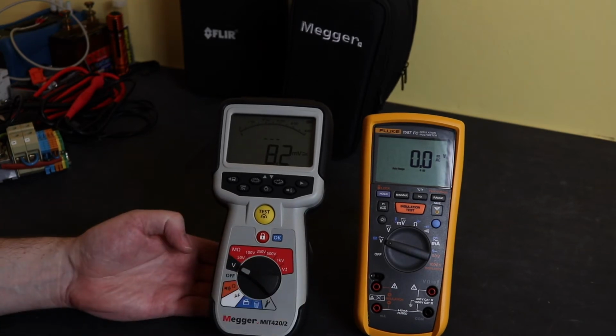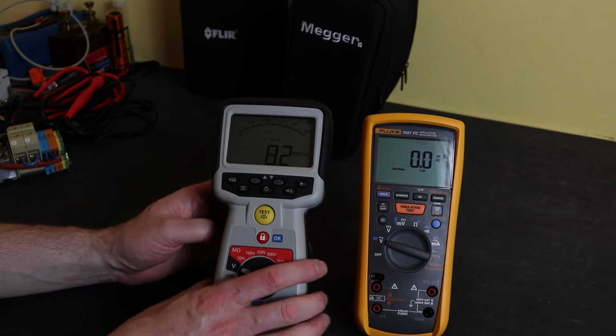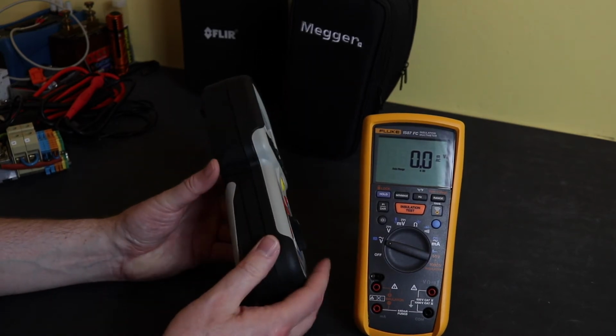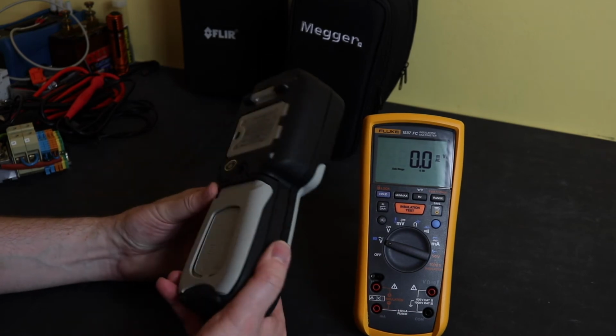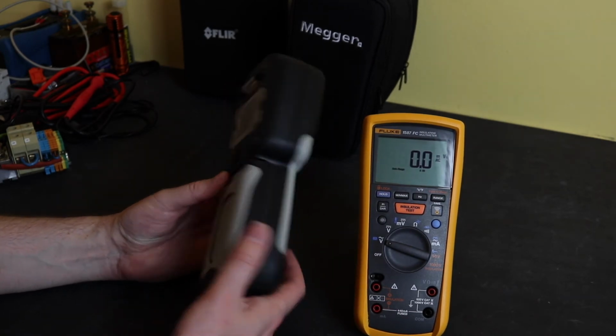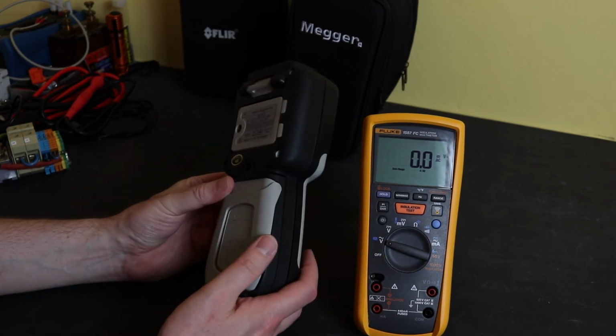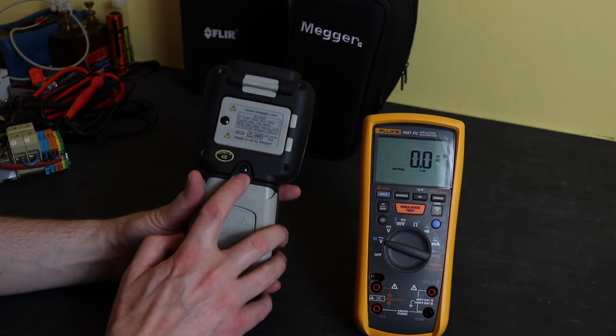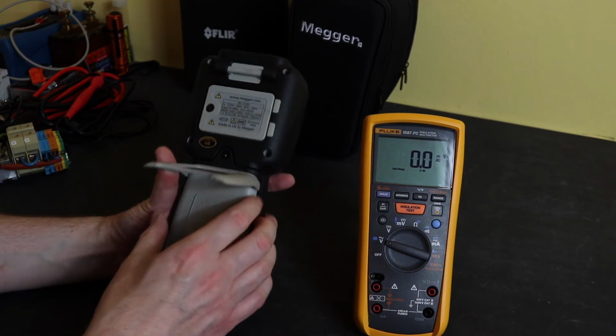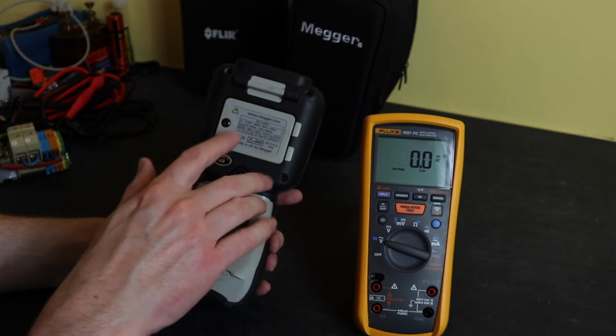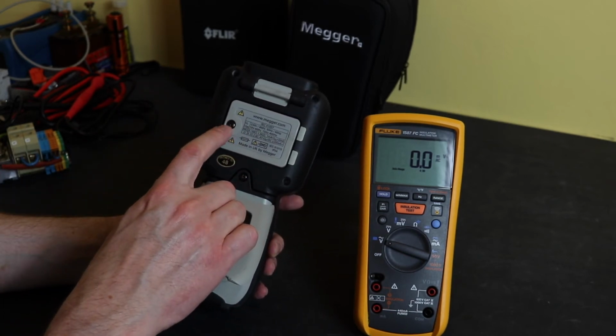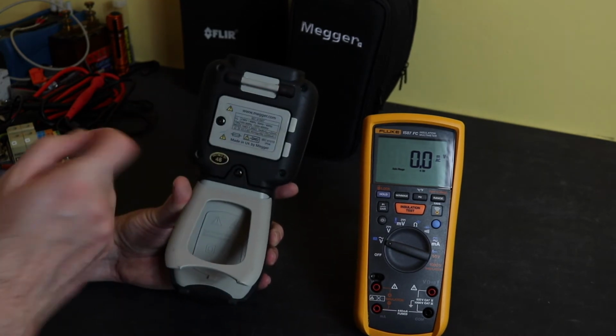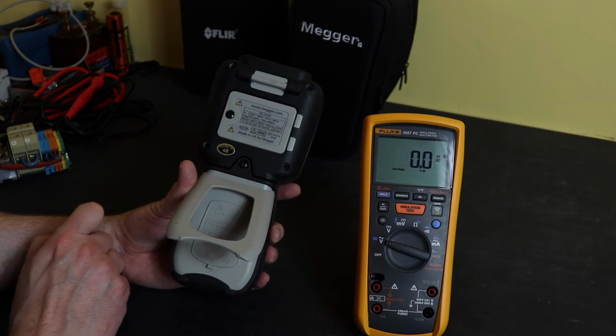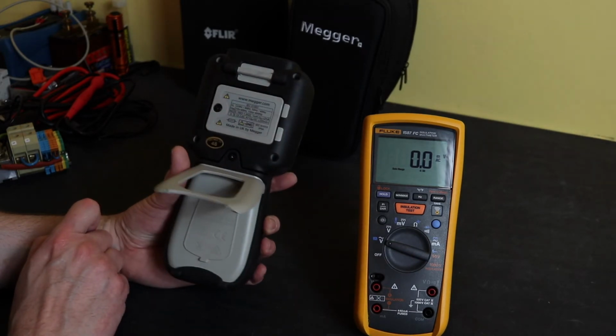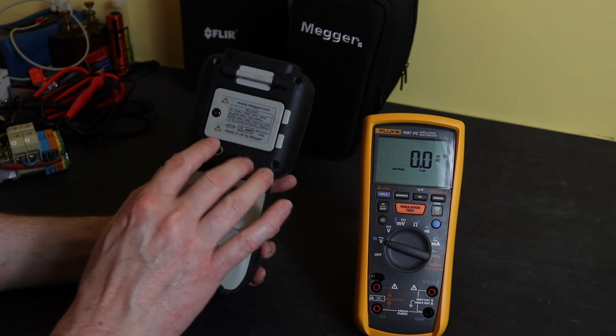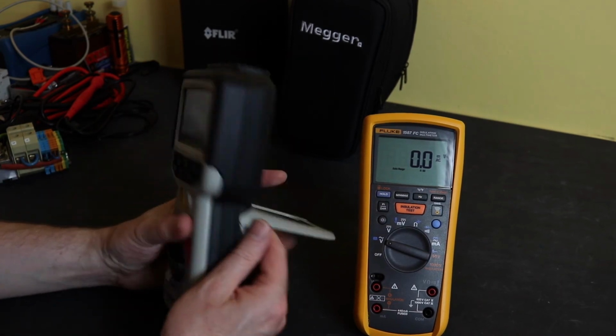Okay, so there's the two instruments. You can see this is the classic Megger case, completely rubber molded onto the hard plastic case, and it's just a box really. Got quite nice ergonomics to it, shaped at the bottom half of the body. The battery compartment here is held in with a single screw, and the tilt bail comes off with everything when you take that one away. And underneath here there's a safety fuse and a separate compartment that you can get to, and you've got the loop up there for a hanging strap, so you can hang the instrument from a panel door or something, but no probe holders on this whatsoever.